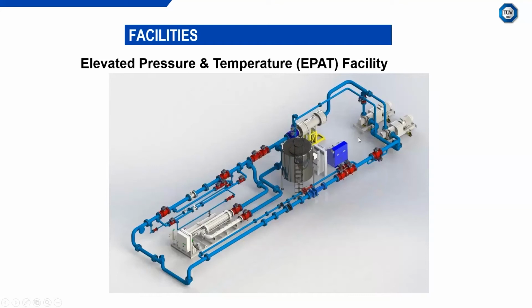It keeps it stable within plus or minus 0.25 bar. In terms of operational conditions, this flow facility operates from 4 to 100 bar gauge, from 20 degrees Celsius to 80 degrees Celsius, and nominally from 0.5 to 100 litres a second. It operates with a mineral oil, with an approximate density in the region of 830 kilograms per cubic meter, and relatively low to medium viscosity of between 2 and 6 centipoise, depending on, of course, the temperature of the facility. Temperature can be kept stable within plus or minus 0.25 degrees C, and that's for the entire calibration. For a specific test point, the temperature and pressure is normally more stable than that.